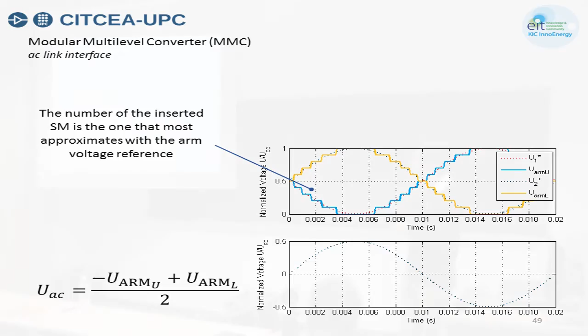If you sum both arm voltages, they equal 1 all the time because it's the DC voltage. So if you are connecting more at the upper arm, you are disconnecting at the lower arm, and so on, in such a way that the number of submodules per phase unit remains constant.